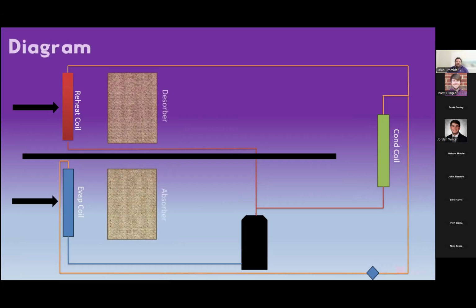Then what we've done is we've put these two pads in here. One is the absorber pad, which again has concentrated desiccant flowing through it. It is picking up moisture, becoming more dilute. It is then sending that diluted desiccant over to the desorber pad, which receives diluted desiccant from the top, gravity fed through the pad.